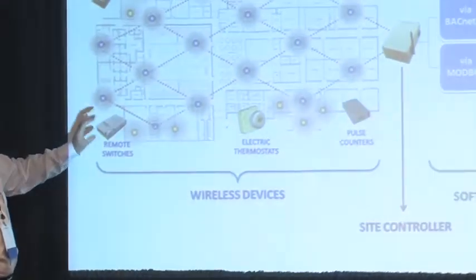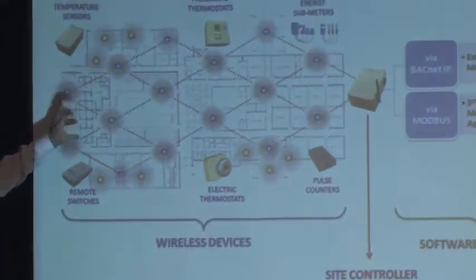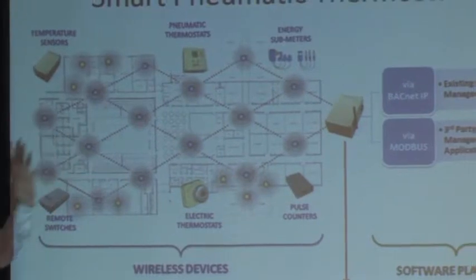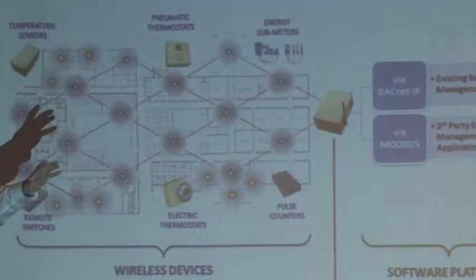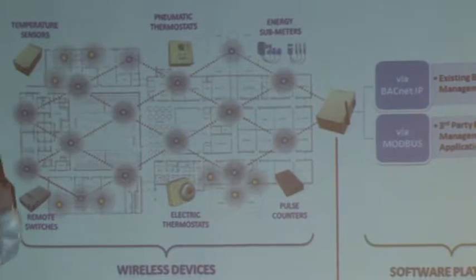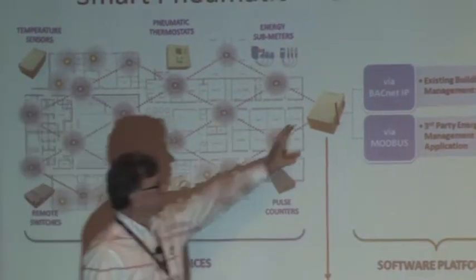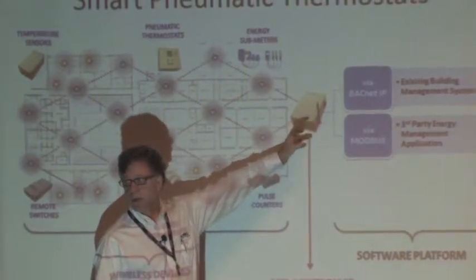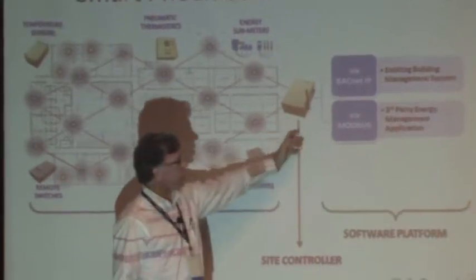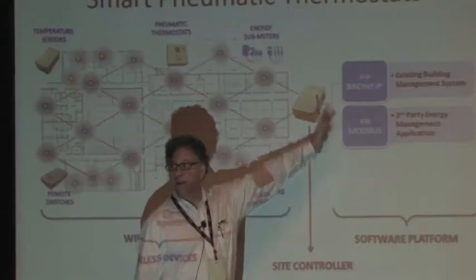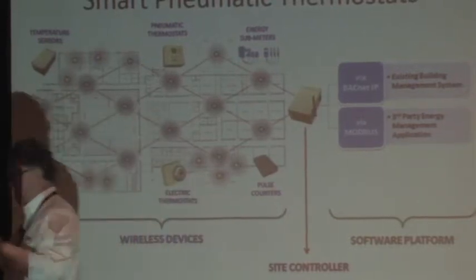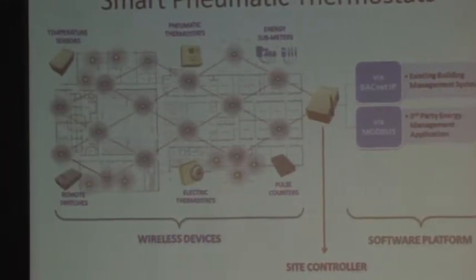So here's again a picture of what you would have in a pneumatic thermostat changeout. A bunch of your thermostats are now changed out to still a pneumatic thermostat, but it's using wireless mesh to have all the digital communications come back, temperature information as well as scheduling information, to the front end. That's going to go to some kind of transponder that takes all the wireless information, converts it into, say, something like BACnet IP, and then goes into the rest of a digital system or a workstation of some sort that's going to do your scheduling and monitoring and alarming on temperatures.